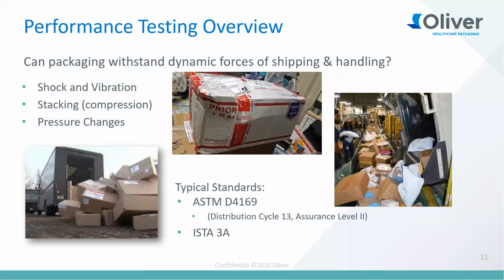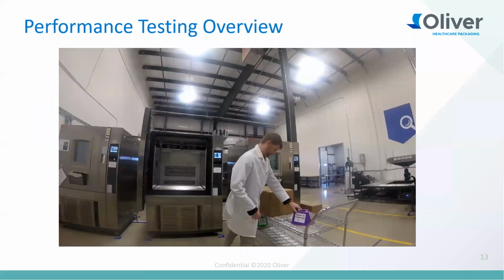So considering things like risk level and unknowns, you may want to go to assurance level 1 and heighten your intensity a little bit. But on the other hand, if you know a lot about your packaging and you have a lot of testing and it's a lightweight, low risk device, maybe a class 1 device, you could consider doing assurance level 3. But of course, just like everything else, you want to have that justification documented. So I believe now we'll go to a video showing some of these steps that we've gone over.